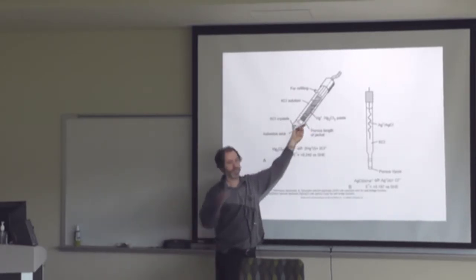A lot of times when I first started working in a lab, I would see the crystals in the pH meter and think, oh, this is bad, this electrode's gone bad. But my boss would tell me, no, that's the way it's supposed to look, because you have the crystals in there. And the silver chloride electrode also contains a lot of potassium chloride, just to keep that always the same too.